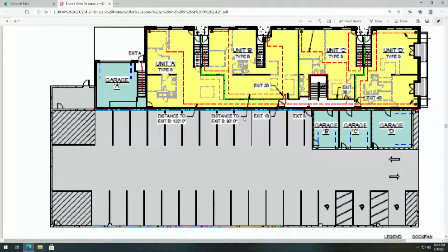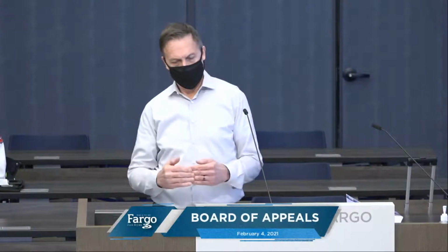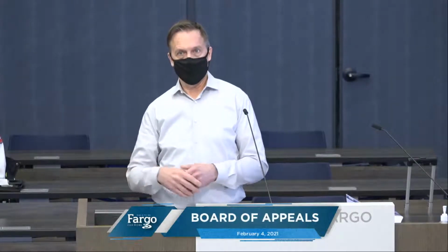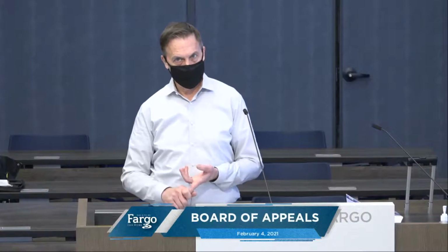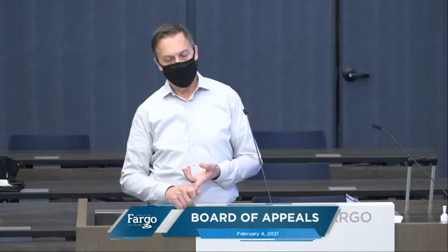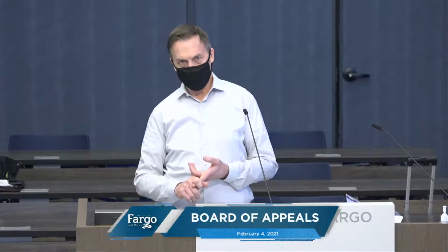Well, the reason we look at 406 is, first, it's more specific, and it gets into the detail of all these garages: public garages, open public parking garages, closed parking garages, private garages, and it's specific for each one. The section that says private garages shall be separated with 1 hour fire barriers, that's clear to us.